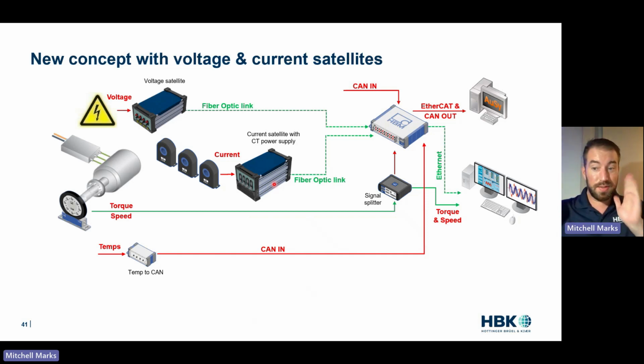So we have less distance to be coupling that high dVdt. We have less copper cable to make it confusing. 4 voltages come into the voltage box, 1 cable back to the unit. 4 currents come into the current box, 1 cable back to the unit. Really try to shorten those measurement cables, bring everything back to 1 common cable. And then from the electrical safety standpoint, we don't have a copper cable coming back to a control room. We don't have a copper cable coming back across the lab.